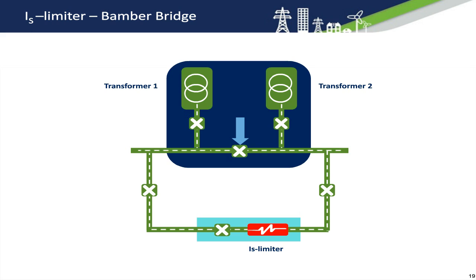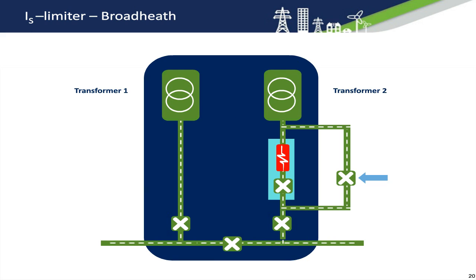The second site is at Broadheath in Manchester, where we're using the IS limiter in a different configuration. At this site we have the IS limiter acting as a closed transformer breaker. The green line and the blue arrow at the right of the slide are just a bypass switch used during the trial and would not normally be installed. If the fault level is exceeded for any of the circuit breakers at this substation, the fault level assessment tool would enable the IS limiter. As before, if a fault then occurs, the IS limiter will operate in 5 milliseconds and effectively open the breaker at the substation, which reduces the fault level any circuit breaker will see, therefore operating safely.